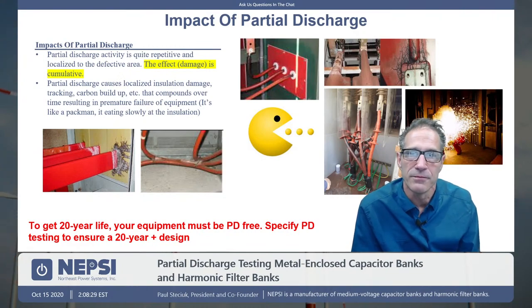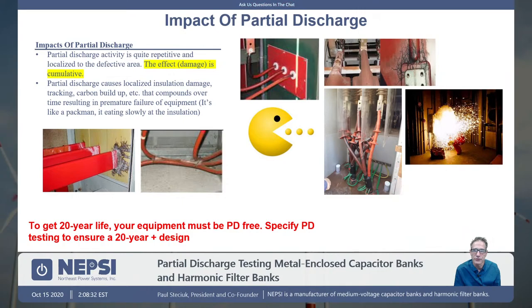So what's the impact of partial discharge? What is damage? You can do a search on the internet, and that's all I did here. I went and grabbed a bunch of figures. Unfortunately, we ourselves even have pictures of our own equipment where we've been sent, by our customer base, damage associated with partial discharge. If I just look at the left here, you can see that there's damage here and really a high voltage here. The white would be from corona on the outside, and the black, I believe, would be more of an effect of tracking, carbon tracking, where you've got damage to the insulation and it's tracking to the wall here.